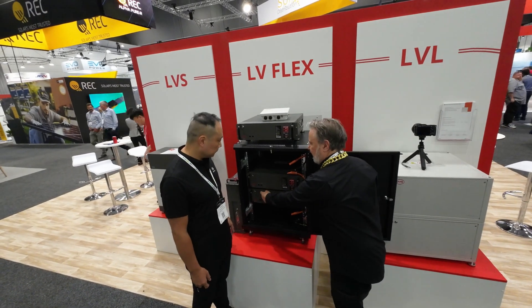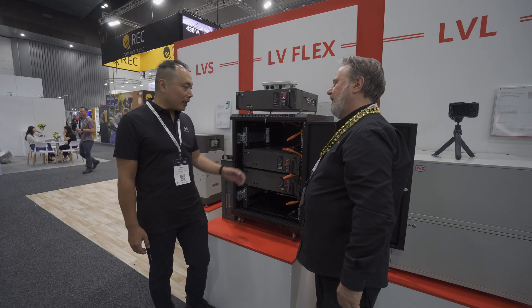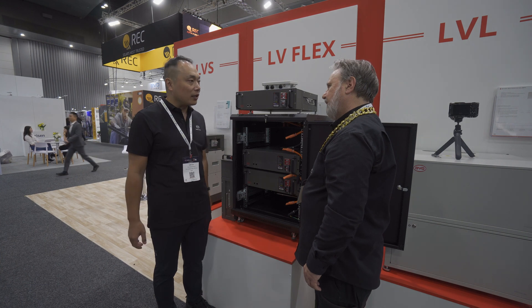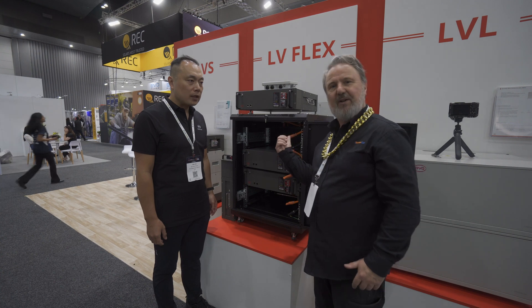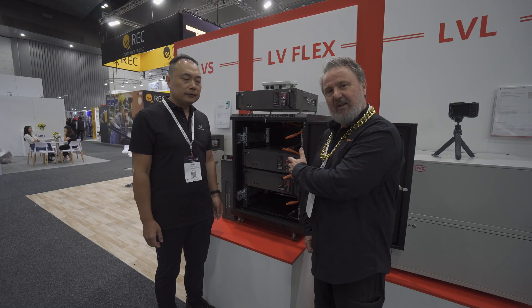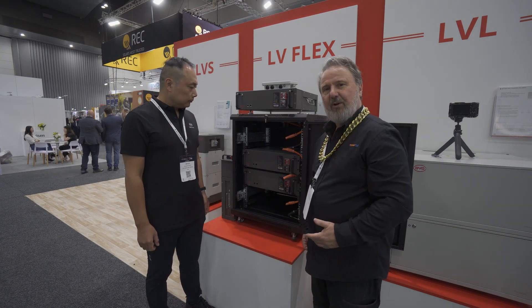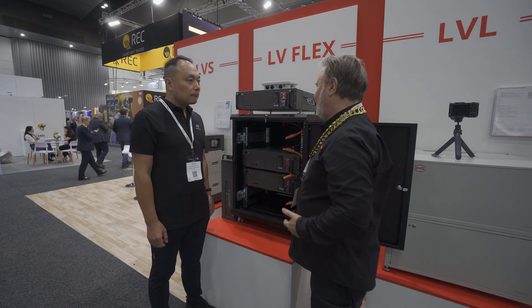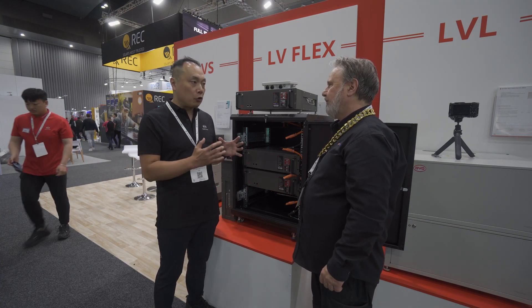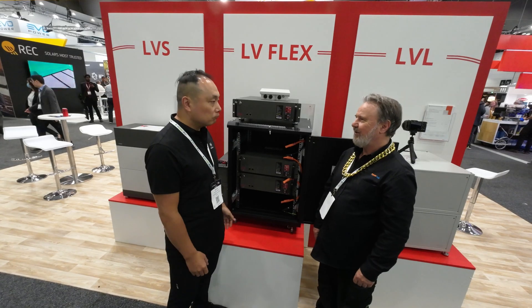64 of these? Yes. And you've got an interconnecting comms cable — daisy chain. In this cabinet we can get four units, that's 20 kilowatt hours in a very small cabinet. The cabinet is pre-wired, so you just slide them in and connect a pre-wired cable. For those familiar with AS5139, this is actually a Section 5 solution, listed on the CEC website for approved products. It can be installed as is — you'll need an external isolator, as it provides battery terminals and over-current protection. It's modular too, standard 19-inch rack, so you can build whatever capacity you need.